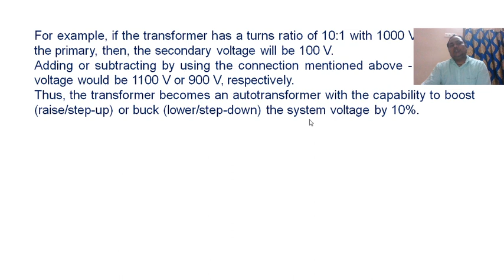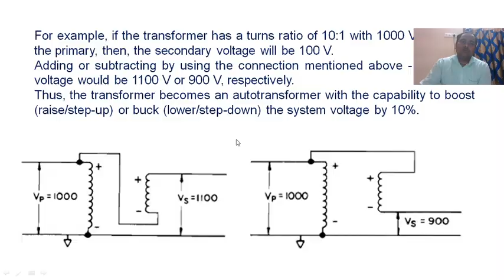Thus the transformer becomes an autotransformer with the capability to boost, or raise, or step up, or buck, or lower, or step down, the system voltage by 10%. So the step voltage regulator boosts or bucks the voltage by 10%. Depending upon the condition, it raises or lowers the voltage up to 10%, depending upon the connection, additive polarity or subtractive polarity.